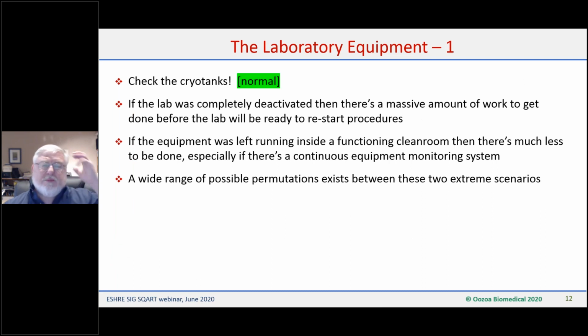In terms of the lab equipment itself, first thing, check the cryotanks. You should have been checking them anyway because that should have been happening, but just have another check and make sure that none of the cryotanks have been showing any diminished performance that might indicate that they're possibly going to fail. You can pick up most tank failures well ahead of them actually failing.